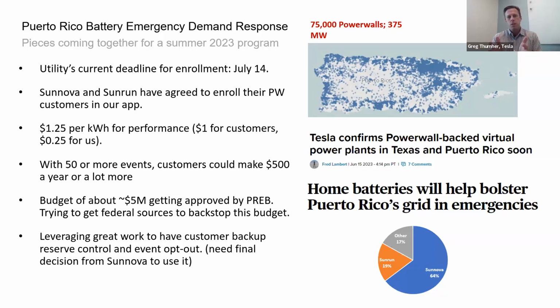A utility system experiencing a transitory or resource failure can often arrest load shed, or forestall or eliminate controlled separations of load, when they have an online and available resource ready to respond. In the case of distributed storage, there are few technologies that can respond faster than inverter-based, paralleled distributed storage systems—in fact, they can respond and be metered in fractions of a second, in the industry known as cycles.